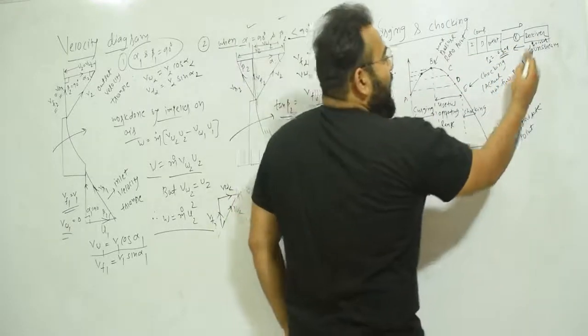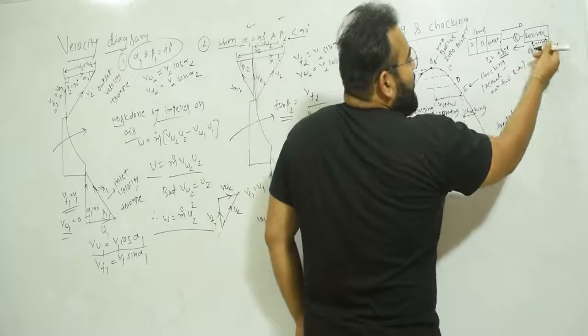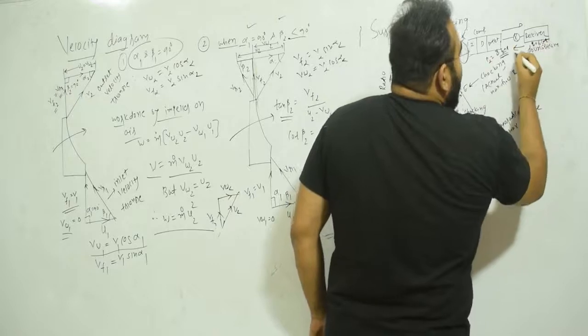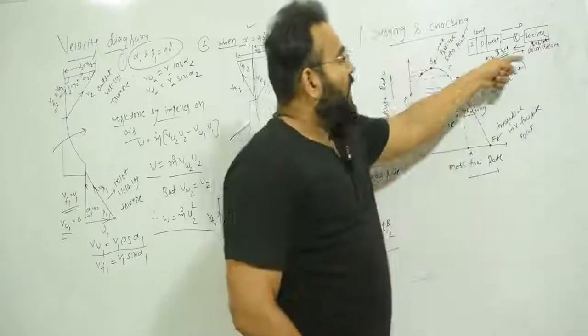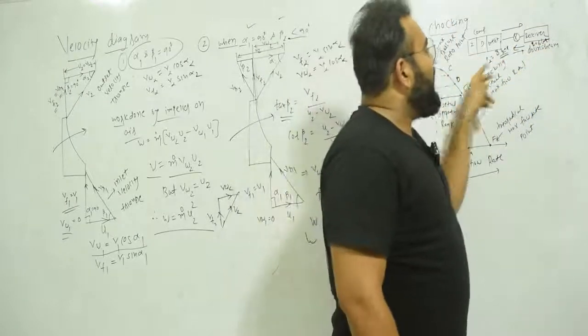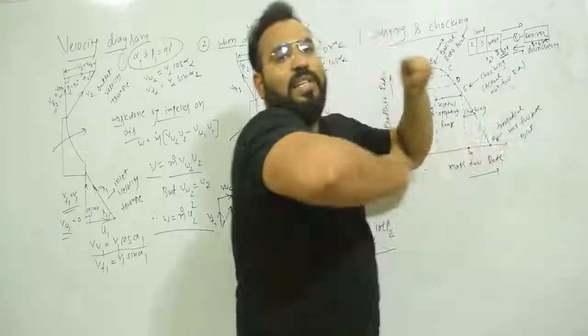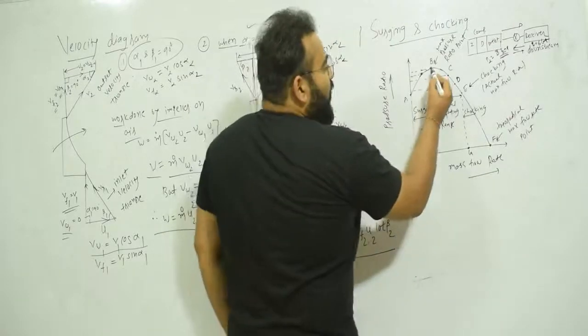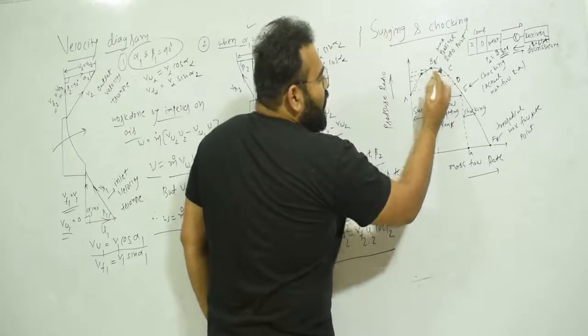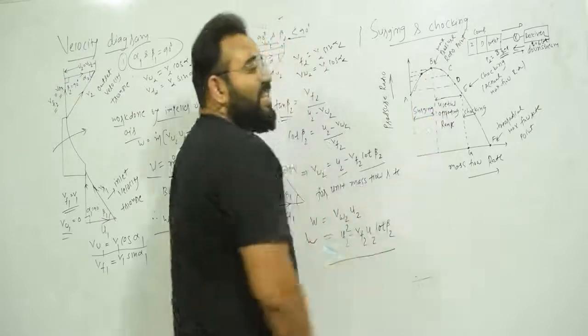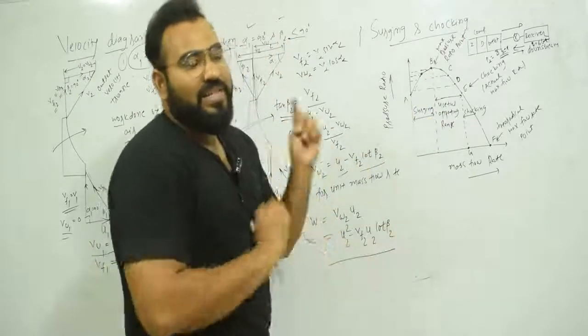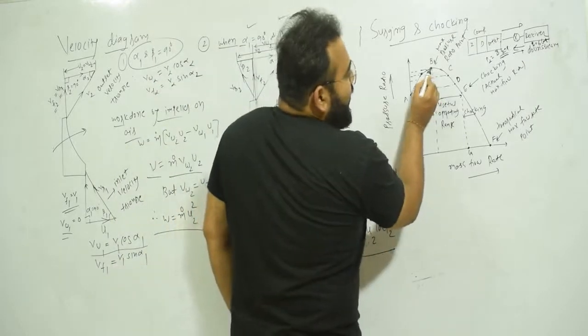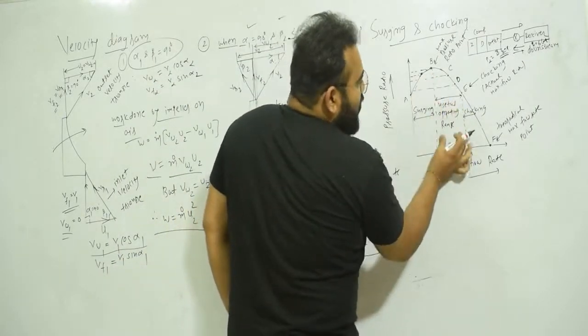After the reverse flow, the storage tank pressure drops — say to 8 bar — while the compressor recovers to 6 bar. Now the forward flow resumes. Then the pressure builds again and reverse flow occurs again. This continuous to-and-fro motion of air is what is known as surging. The entire region from point B to point A is known as the surging region. The useful operating range is between points B and E.